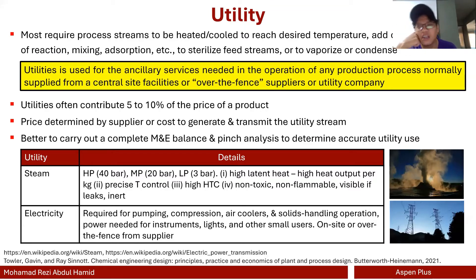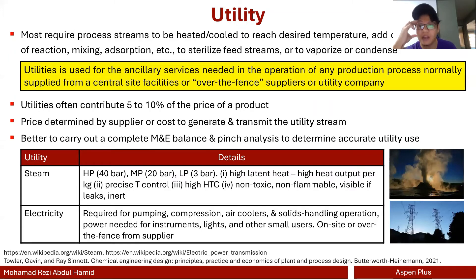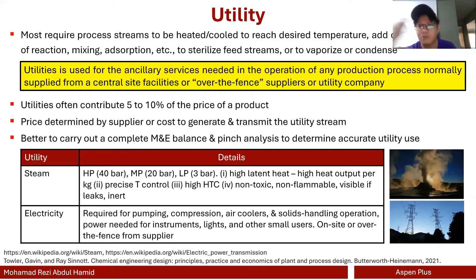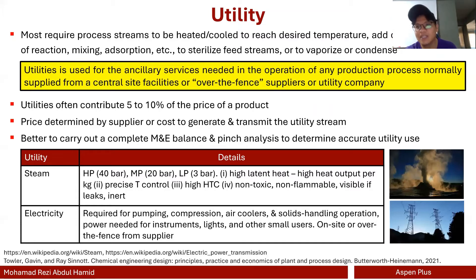Steam is good because its latent heat is quite high, it's non-toxic, and it allows precise temperature control — meaning we just need to play around with the pressure. If we talk about saturated steam, we play around with the pressure to get the specific temperature we want. If there's a leakage, we will see the steam coming out, so it is visible. We also have electricity to run compressors, pumps, and things like that. Electricity can be generated on-site or obtained from over-the-fence suppliers.